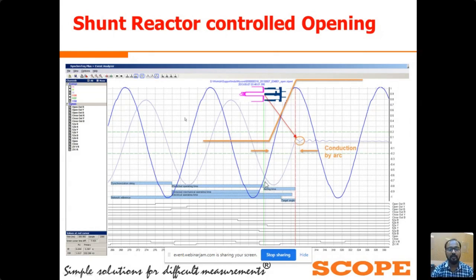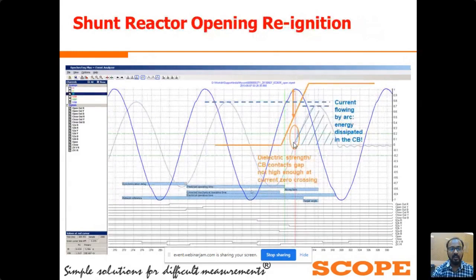By opening the CB contacts in the reignition free window, we have avoided the reignition of current between the CB contacts. So this is the waveform and the switching operation using the controlled switching device. Now we will see the random opening operation of the shunt reactor. This is the waveform we recorded when the CSD was in out of service mode. Here the waveform in dark is the system voltage waveform, and the waveform in light blue is the current waveform, which breaks here. This is the breaker operating time.